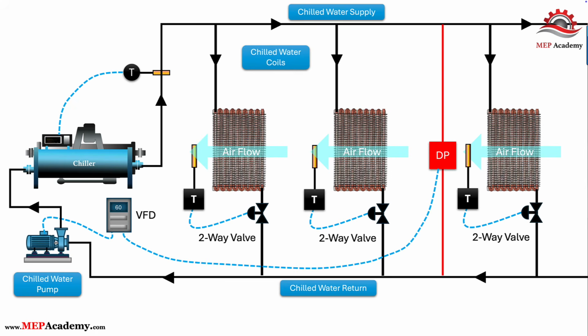Next, install a differential pressure sensor to monitor system pressure as the control valves close. As differential pressure increases, the controller sends a signal to the VFD to reduce pump speed, lowering energy consumption. Finally, verify that the chiller receives the minimum flow required for proper operation. Install a bypass line between the chilled water supply and return near the chiller, sized to maintain minimum evaporator flow when most valves are closed.